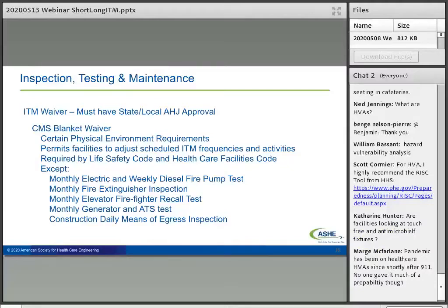There are a few things submitted to CMS that were not accepted as part of the blanket waiver: the monthly electric and weekly diesel fire pump tests must continue, monthly fire extinguisher inspections must continue, monthly elevator firefighter recall tests, monthly generator and ATS tests, and construction daily means of egress inspections.